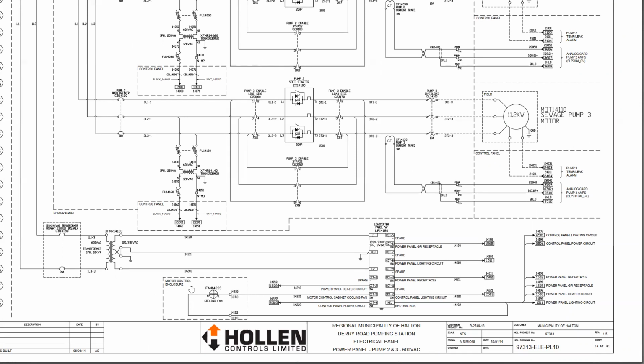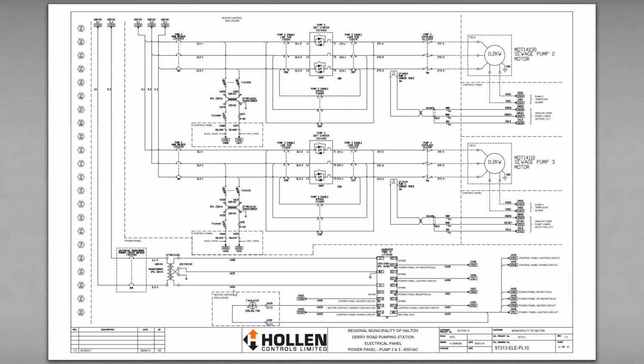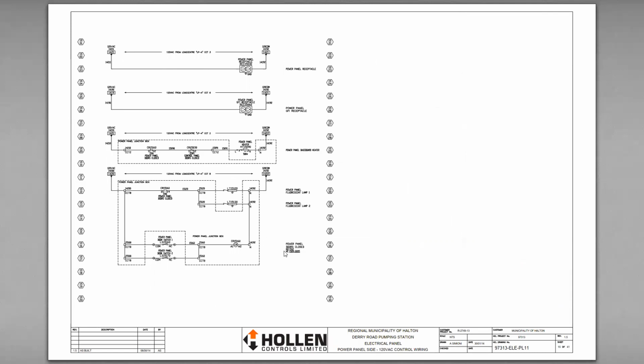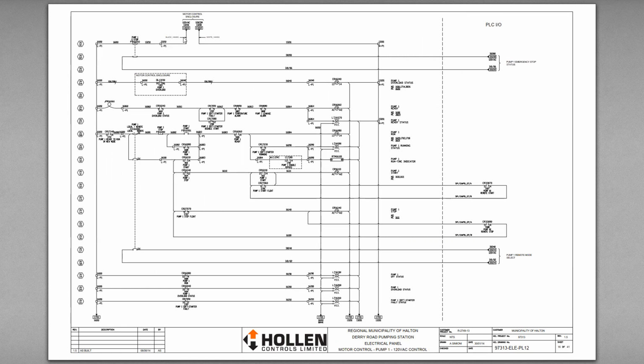There was an air conditioner for this panel because it's stainless steel and it sits on the side of the road. These are the door contacts for lighting, for security system. If somebody were to break into this panel, they could do a lot of damage by shutting those pumps off. So that's alarmed. This is the control circuit for it.